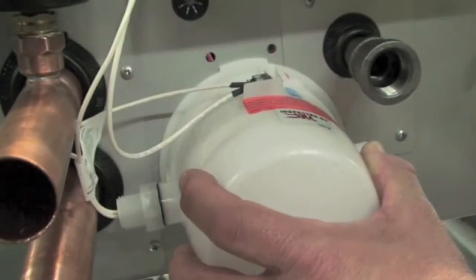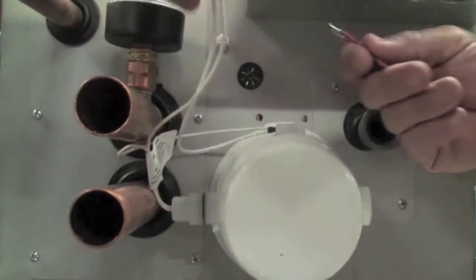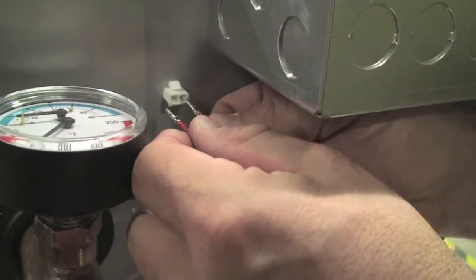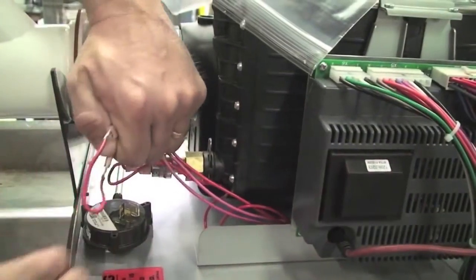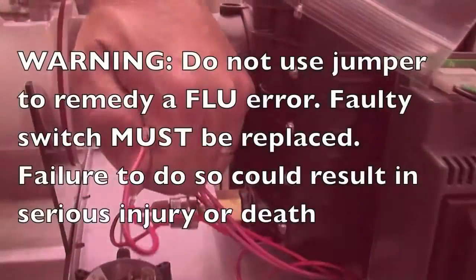Correct any problem found and resume operation. If the code is still present, then jump out the blocked vent switch and the condensate switch to determine what is causing the failure. Never leave the unit jumped out. Replace the part and resume operation.